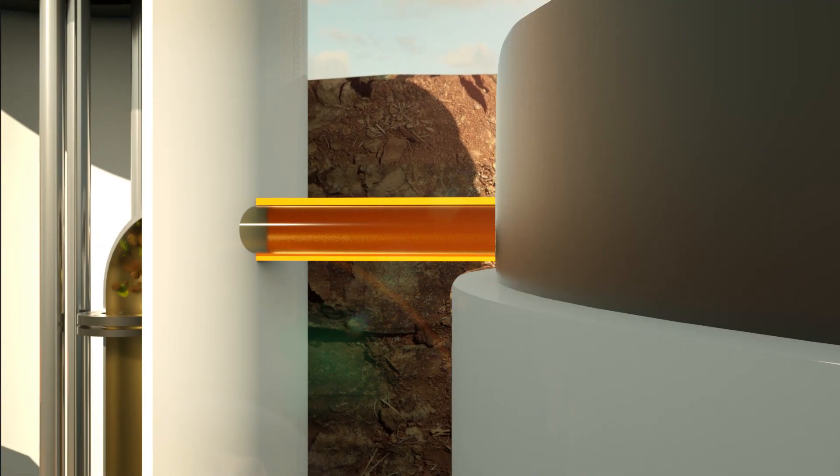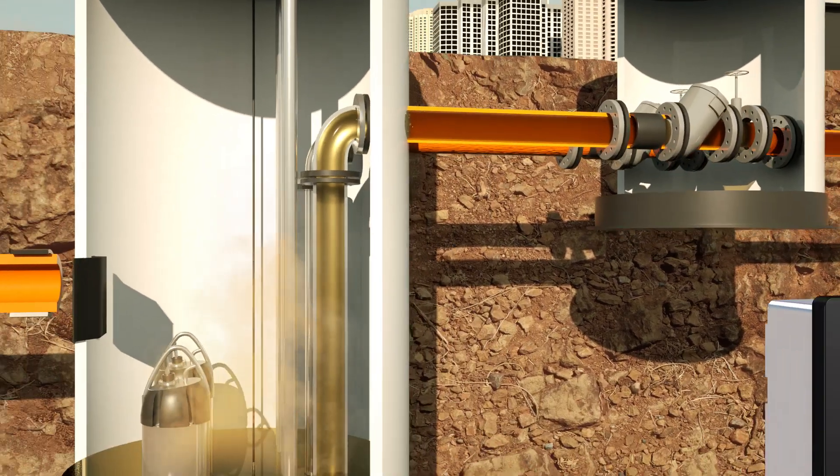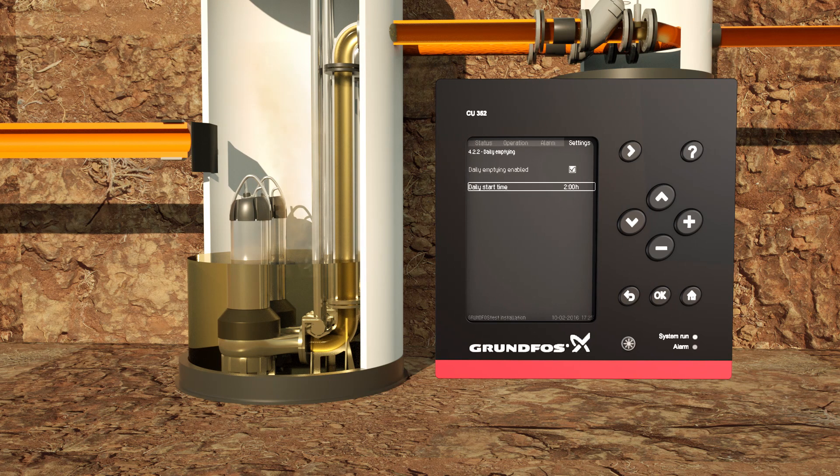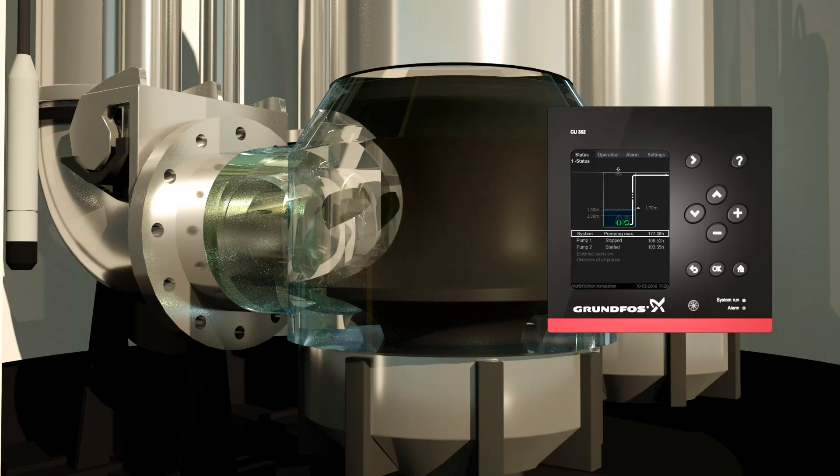To avoid stagnant conditions in the pit, which may lead to sedimentation, accumulation of solids inside the pit and finally odor formation, the control system ensures daily emptying of the pit. This also prevents the pump from blocking.